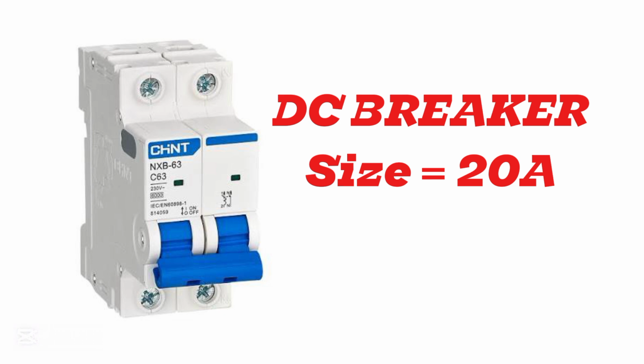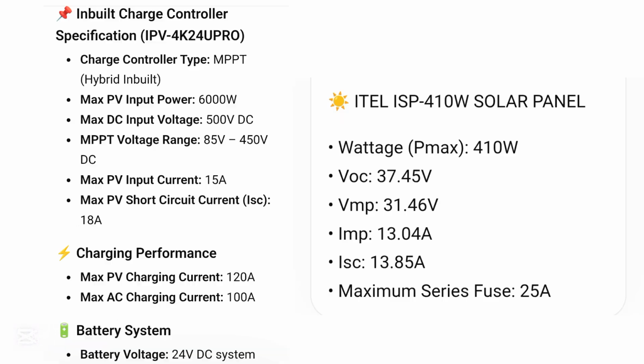Now, the first thing in the list of accessories we bought is the DC breaker, and the size we bought is 20 amps. So how do we arrive at 20 amps? Let's break it down. Here is the specification of the inbuilt charge controller on the left and that of the solar panel on the right. The operating voltage range of this charge controller is 85 volts to 450. So it means that whatever we are doing, we are not going to exceed that voltage range.